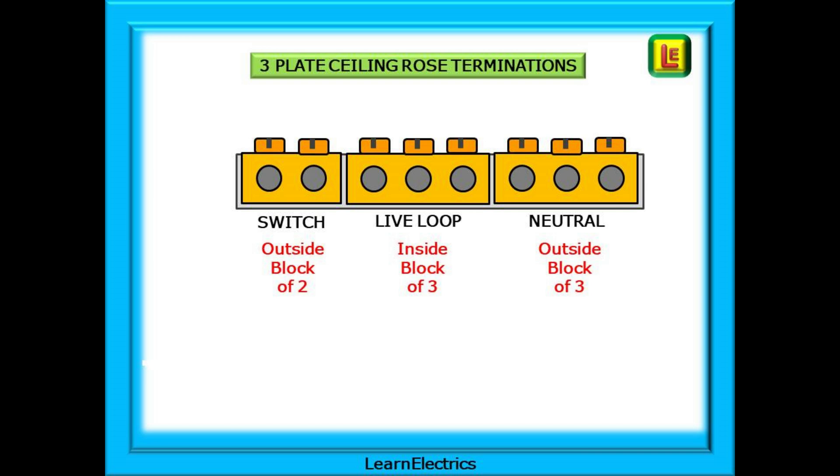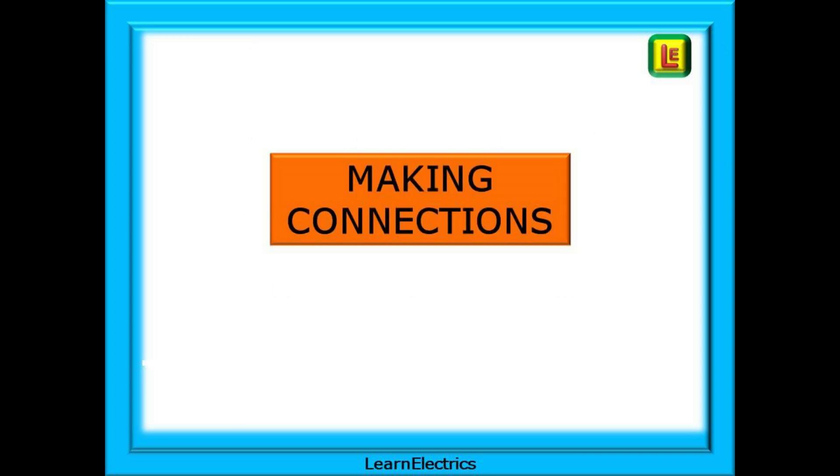We always designate the brass terminal blocks as follows: the outside block of two is used for the switch wires, the middle block of three is the live loop block, and the outside block of three is the neutral block. Let's look now at how we make the wiring connections inside the ceiling rose, and how we shouldn't.